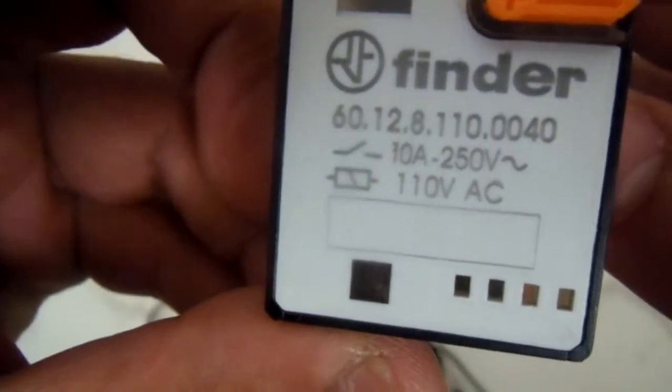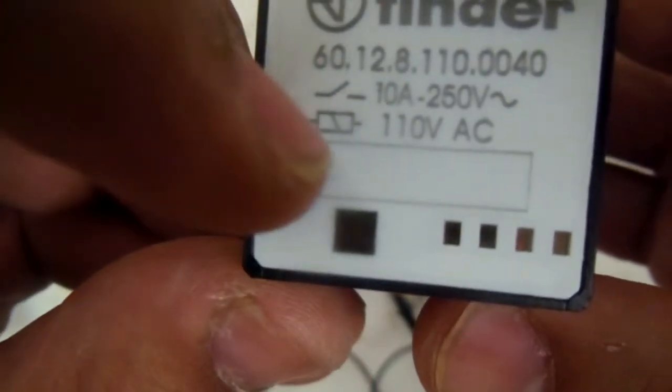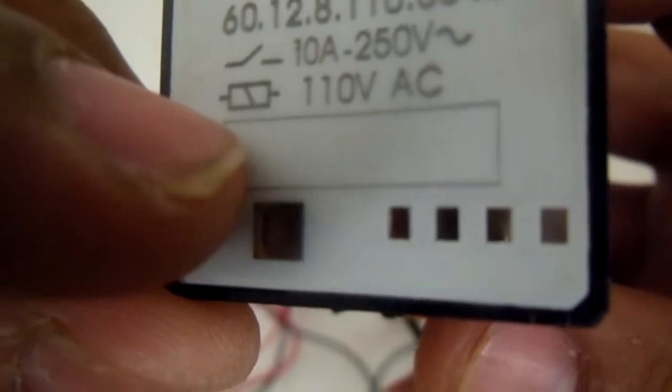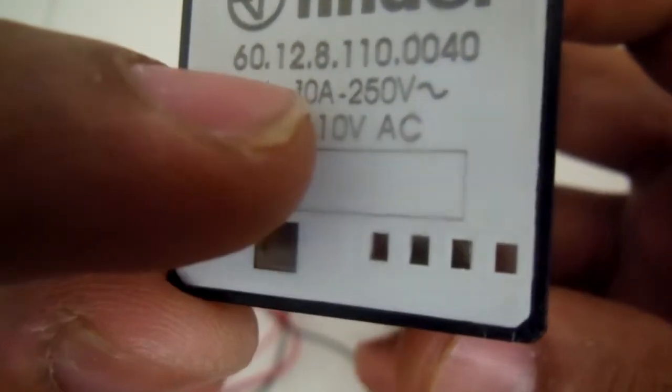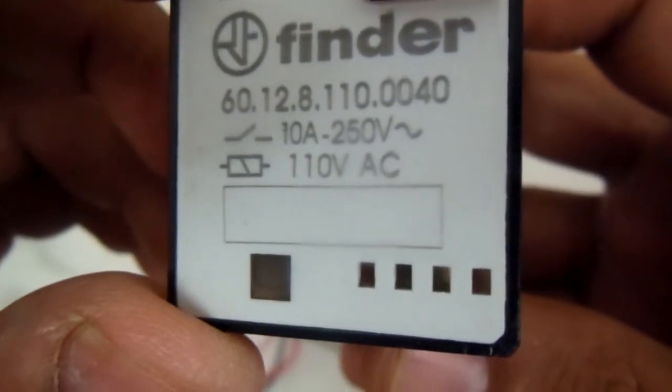And these are also AC relays, 8-pin AC relays. This relay can control 10 ampere AC, and it operates on 110 volt AC. So it is an AC relay. We cannot control it by DC current. By a small AC we can control a large AC. For example, with 110 volt AC and about 10 to 30 milliampere AC current, we can control 10 ampere AC current at 250 volt AC. These are the kinds of relays.